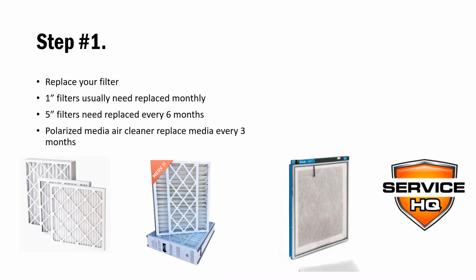So you can see these pleated filters here. This is a 5-inch filter here. Well, the dirt fills up the valleys first and then works its way up to the top of the pleat. So that's why you can get more extended runtime out of those type filters. And then we have a polarized media air cleaner. You replace those media every 3 months.